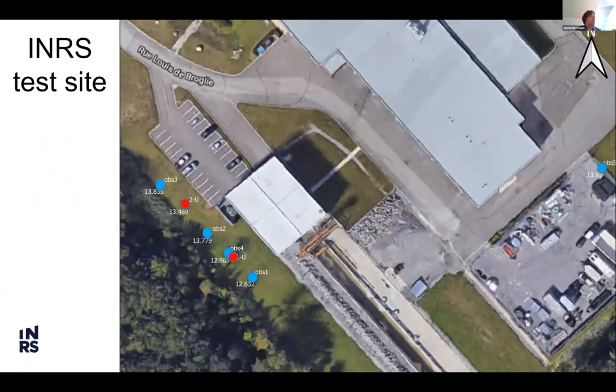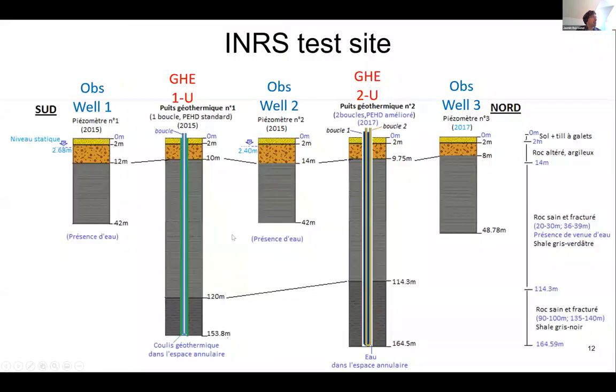So what we've done at INRS is try to improve those ground heat exchangers with a pilot test site that we have at our lab facility. We have a site with different heat exchangers: a conventional double U-pipe, an unconventional double U-pipe ground heat exchanger, and a conventional single U-pipe, and also some observation wells in between to monitor the ground when we do tests.